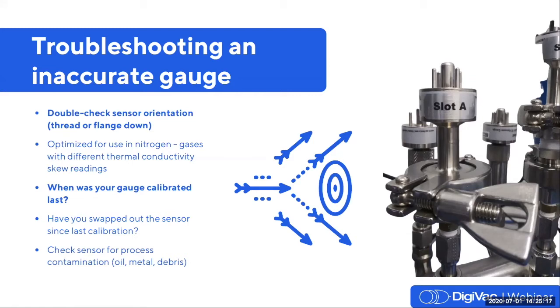Well, we spoke about how we generate heat with a filament and then read the heat using the other filament. Well, the heat generated by the first filament won't diffuse into other gases the same way that a nitrogen-rich air, for instance, breathable air, will accept the heat. There are fewer molecules and different molecules to absorb that heat, so it absorbs it differently, which skews how the gauge reads vacuum. This doesn't mean that thermocouple instruments are useless in non-nitrogen rich or ambient air systems. However, it does mean that you'll need to do a bit of conversion to ascertain what your actual vacuum level is. And at DigiVac, we can provide a comprehensive thermal conductivity gas conversion chart to figure out exactly what your gauge is reading.